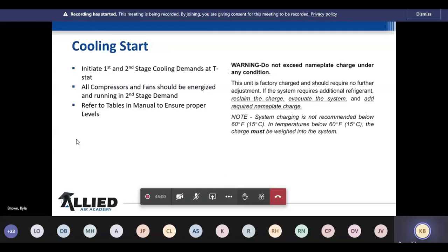So we want to make sure we initiate first, second, third stage cooling. The reason for that is if you look on the side over here, if it's below 60, weigh it in. But the important part for this: initiate the first and second stage cooling, and all compressors and fans should be energized and running to ensure the proper levels.